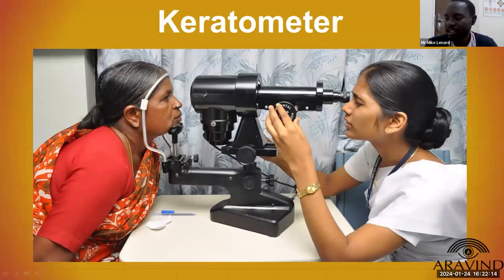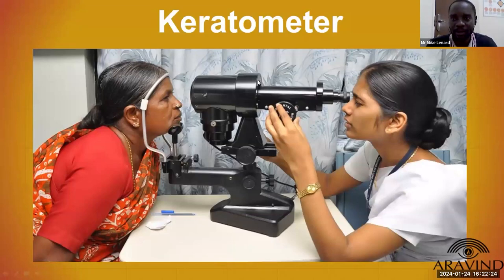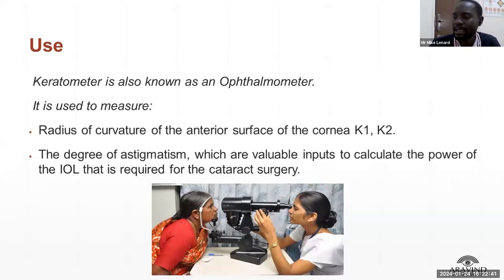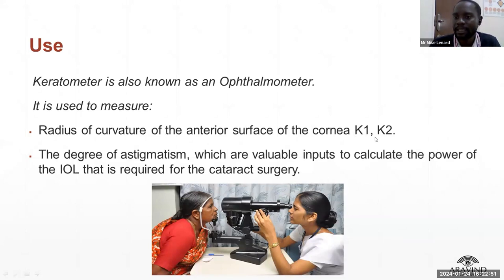Today we are going to share about the keratometer. It's an important piece of equipment used in most ophthalmology settings. A keratometer is also known as an ophthalmometer, and it's used to measure the anterior surface of the cornea — specifically K1 and K2.